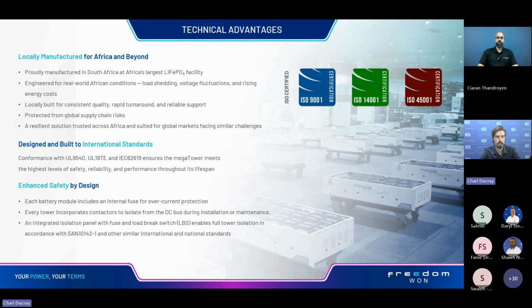Something I really like that you and your team did is on the safety side: you've ensured that every single battery module includes an internal fuse for overcurrent protection. That's an additional safety measure that falls outside of the BMS's safety features. For us, we don't compromise on safety. So even though every module is in series in a single tower, we still decided to go that extra step and put a fuse in every module.